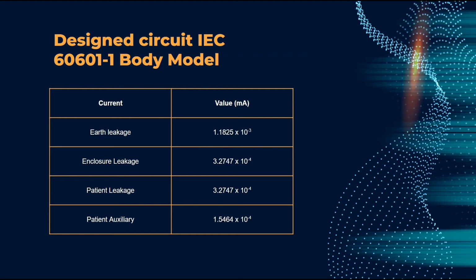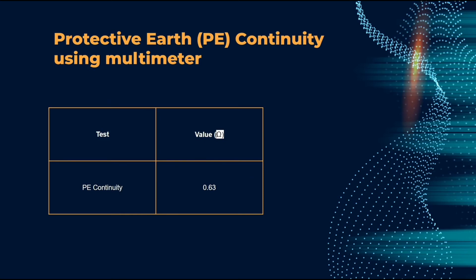Then we conducted the test using the designed circuit. We can find 4 different values of current using our designed circuit: earth leakage current, enclosure leakage current, patient leakage current, and patient auxiliary current. Then the last test we have done is quantitative earth continuity using a multimeter, PE continuity. This is the only test we have done using the multimeter. So we got the value of PE continuity at 0.63. That's all for the results part. The next part will be explained by my group member, Abdullah.